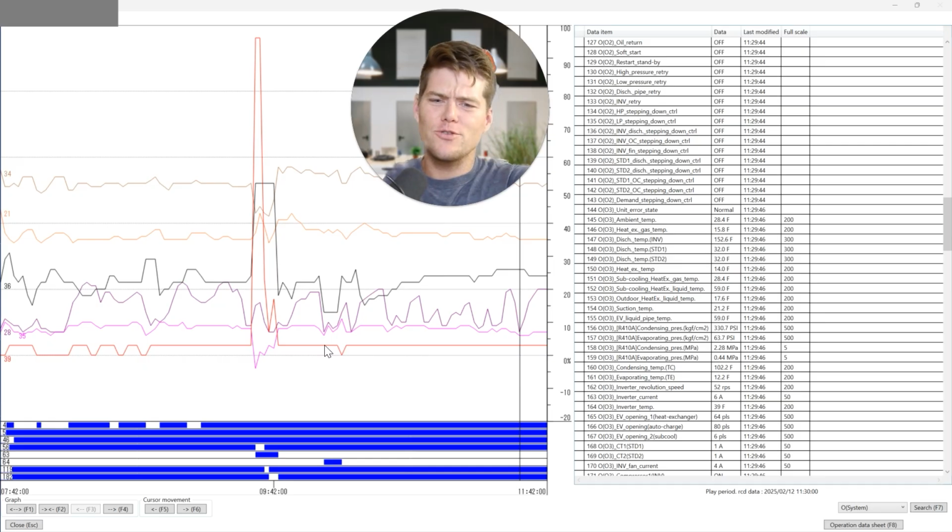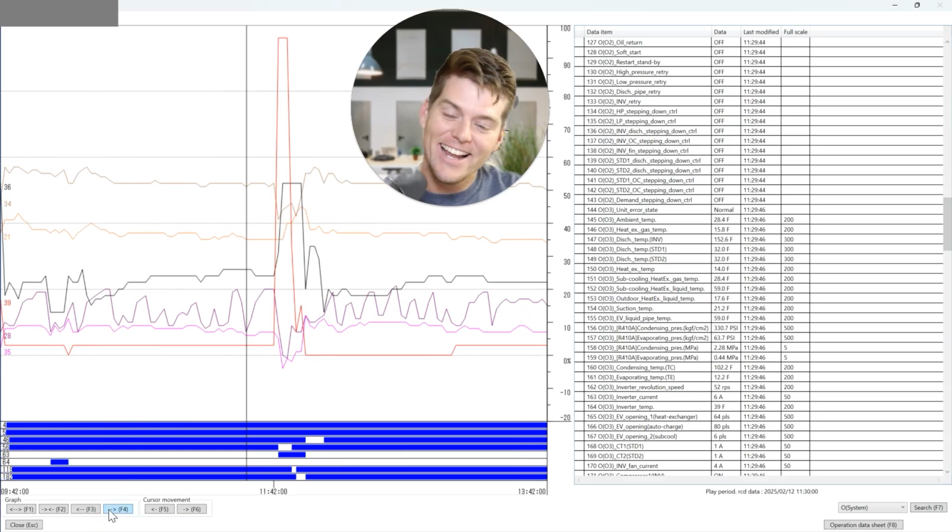You see a screen full of squiggles here, as you should with service checker data. And what the heck are we looking at? A friend of mine reached out, said he's lost a compressor, 2 compressors. Actually, this machine has probably eaten an unknown number of compressors like a lot of VRF systems do. And the data doesn't make any sense.